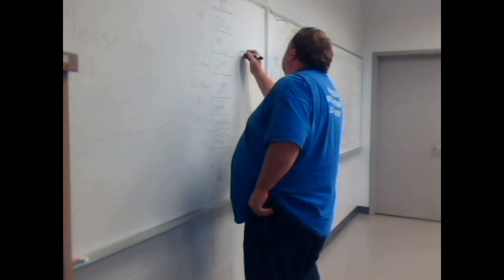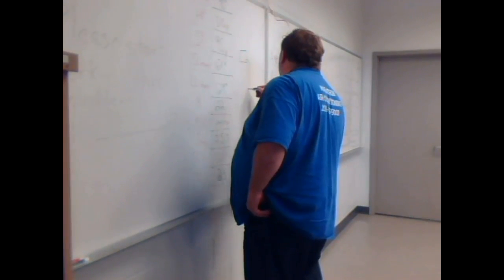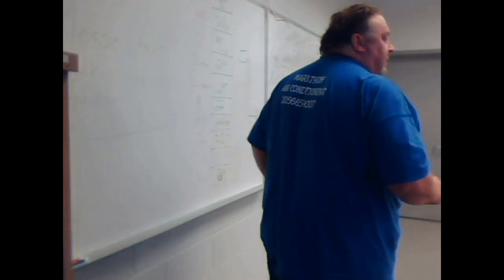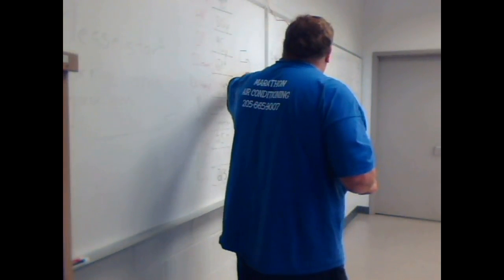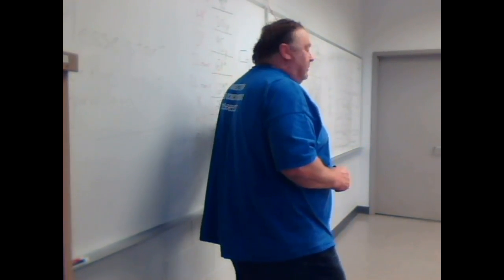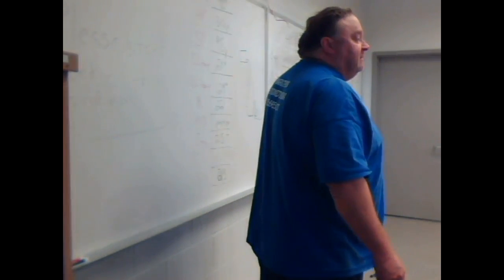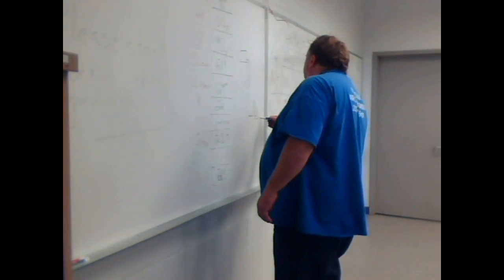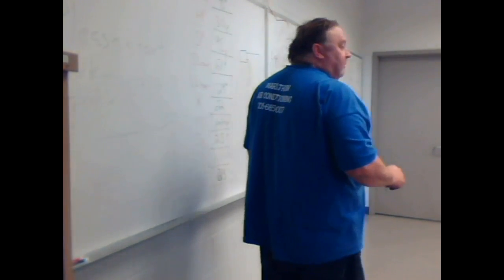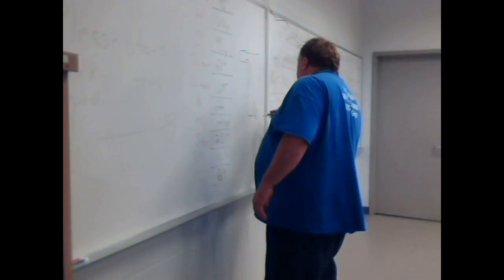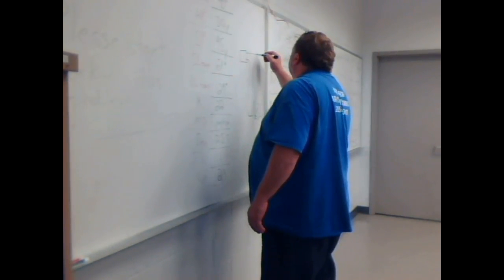So, when you design this system, you always put a trap. In other words, let's say my condenser's here and my evaporator's here, okay? We run this line down, right? You want to go in here, right? But if this system stops, I don't want all this filling my evaporator coil. So we would always come out and put a trap, enough to hold it. Probably five inches is more than enough. Same way coming back out, I run back up here with my suction line, I got oil, right? I don't want it running back in here, so I'm going to build me a trap. And I would usually put a trap up here too.